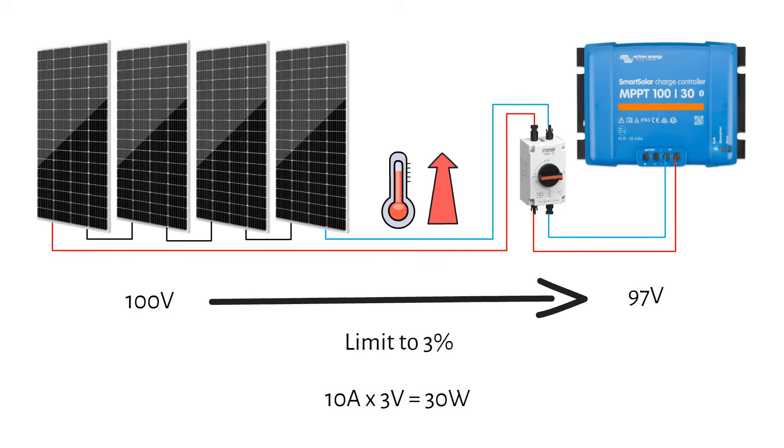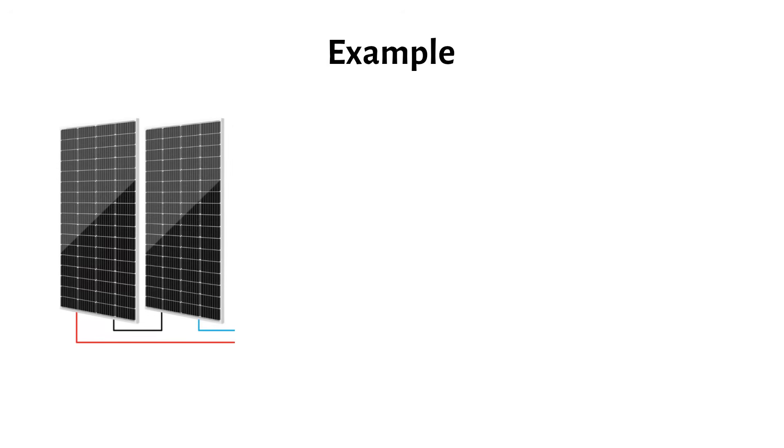In a typical off-grid system, the cable between the solar panels and the MPPT is usually the longest run, so that's where it makes sense to calculate the voltage drop. Let me show you how we calculate it using an example. We will use two 200 watt panels in series. These are the panel specifications.